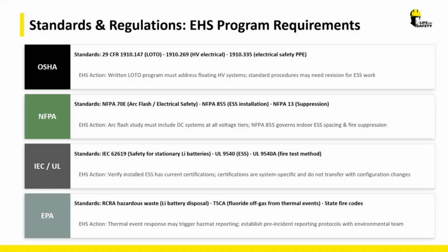Most likely that one's not going to be one we can use very often, just because these cells, unless depleted completely, have stored energy. And when they're constructed in series and parallel circuitry above 50 volts, the lockout-tagout standard applies.